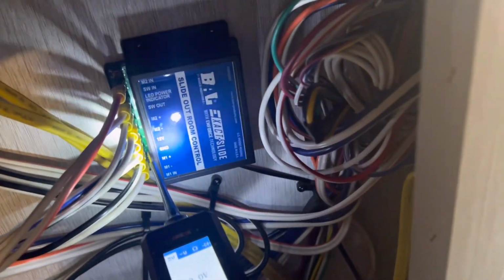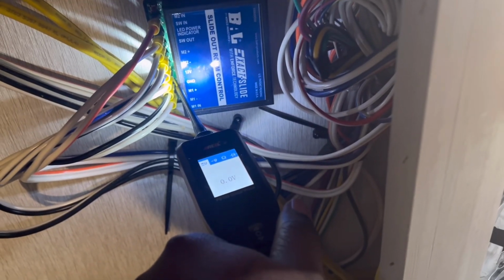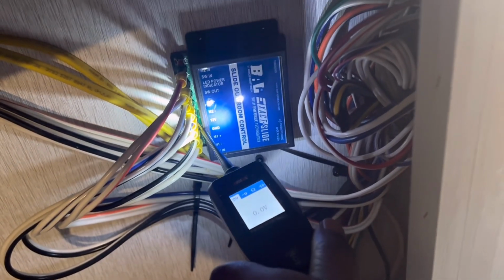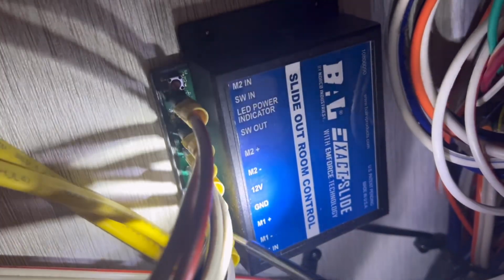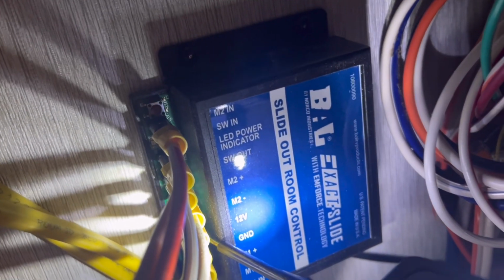Once we do that, we can come in here with our probe and check for power. This controller has power of its own, and you can come in here and check for that power using your probe, and that's going to be on the blue and purple. So you can see we have our ground, and we have our power. Okay, and then you do the same thing to test the switch.